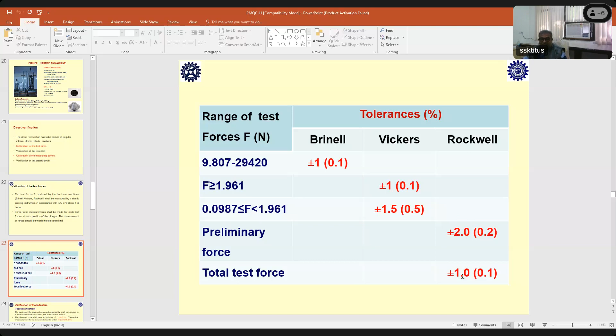And if your machine is not satisfying any of these things, in the case of Rockwell also it is mentioned, if the machine is not satisfying any of these requirements, then it cannot be used as a calibration machine or testing machine. You have to be very clear about it. And in the case of Rockwell, the application of preliminary force can be plus minus 2.0 and 0.2 for the calibration machine, and the total test force is 1 and 0.1%.